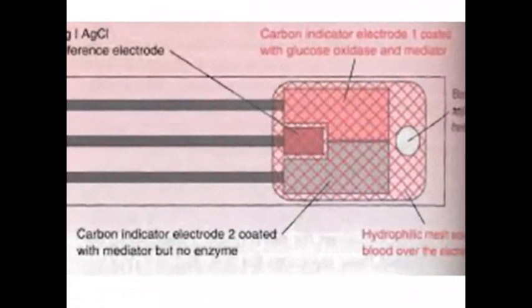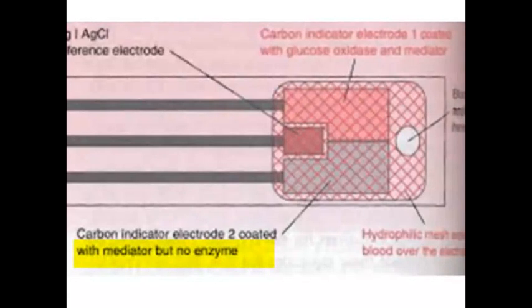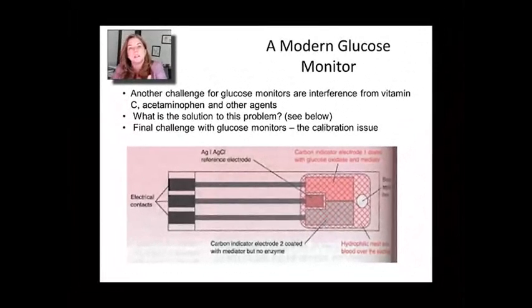They deal with it because they built an extra electrode. At the bottom is indicator two electrode which has the mediator, the ferricyanide-ferrocyanide couple, but doesn't have glucose oxidase. If you get a signal from that second electrode, that's an interfering agent and you can subtract it from the total signal. That's a clever way to deal with interfering agents because glucose oxidase really only reacts with glucose. You can correct for vitamin and other substance interference this way.